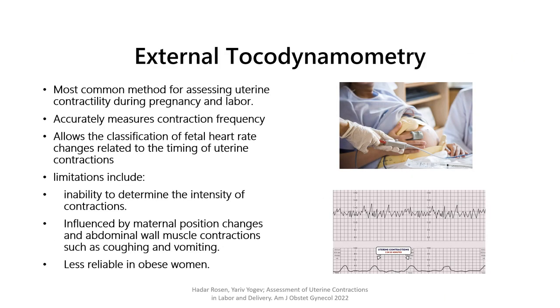External tocodynamometry is the most common method for assessing uterine contractility during pregnancy and labor. It accurately measures contraction frequency and allows the classification of fetal heart rate changes related to the timing of uterine contractions. Its limitations include the inability to determine the intensity of contractions, and it is influenced by maternal position changes and abdominal wall contractions such as coughing and vomiting, and is less reliable in obese women.